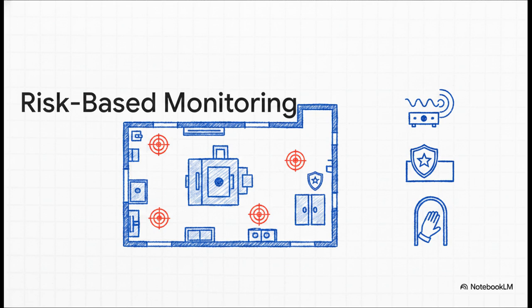You need continuous Grade A non-viable monitoring throughout processing, coupled directly with viable monitoring of that critical zone. On top of that, personnel absolutely must be monitored via glove and gown prints as standard practice the moment they exit aseptic work. Every single sampling point needs a solid, defensible, risk-based rationale behind it.